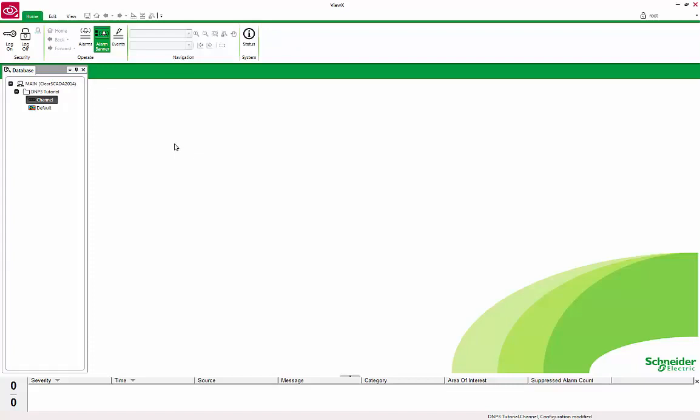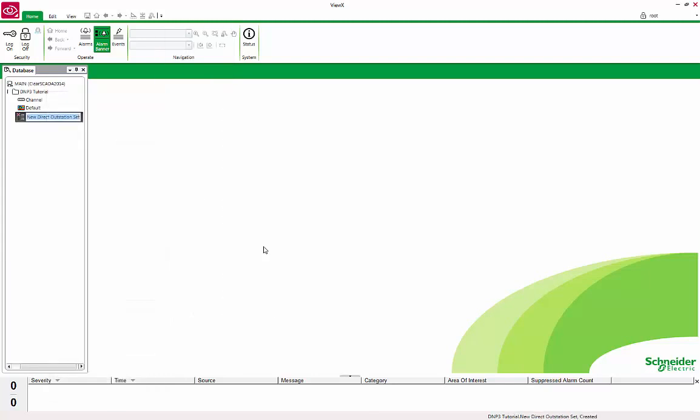The next object we need to create is called an Outstation Set. This defines a group of devices or Outstations as they are called in ClearSCADA. Right-click on the DNP3 tutorial group, Create New, DNP3, and select Direct Outstation Set. Rename it to Set.